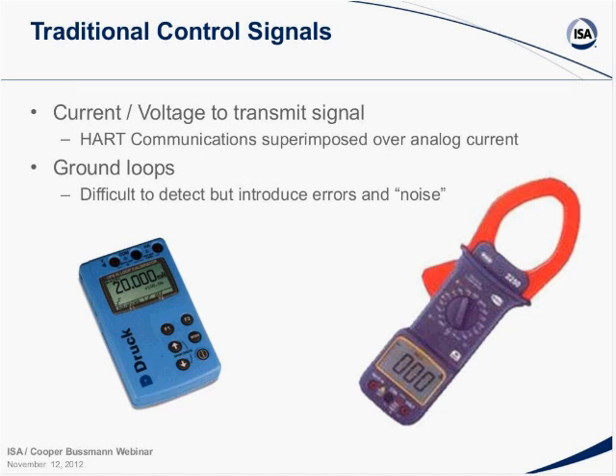So those are all the IT-type tools that transfer over to Ethernet in the control domain. But we also have traditional control signals at the field level - current and voltage. HART is a superimposed digital signal over an analog current, but we really do use the current as the PV.